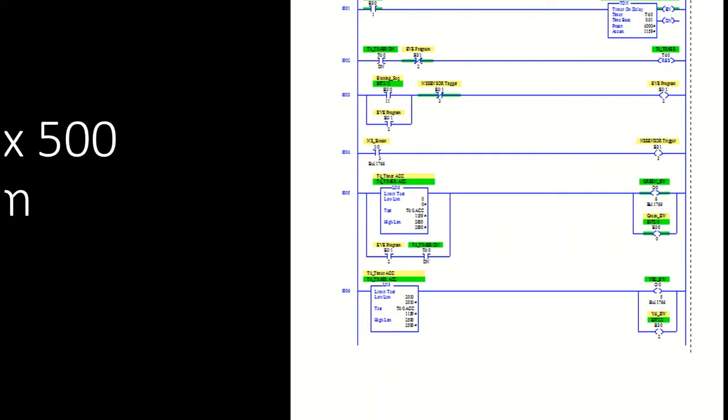add in the nighttime routine and have a smooth transition between the daytime and the nighttime scheme. The latches were preventing us from having a smooth transition from the daytime to the nighttime scheme. Once the nighttime was triggered, instead of ending the day cycle, it would move immediately over to the nighttime routine, and that's not what we wanted. We wanted that once night is triggered, we smoothly end the daytime sequence and then transition into the nighttime sequence. Once we removed the latch and unlatch, we were able to set that up.